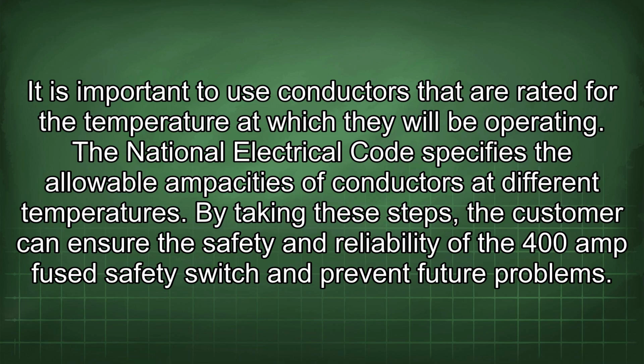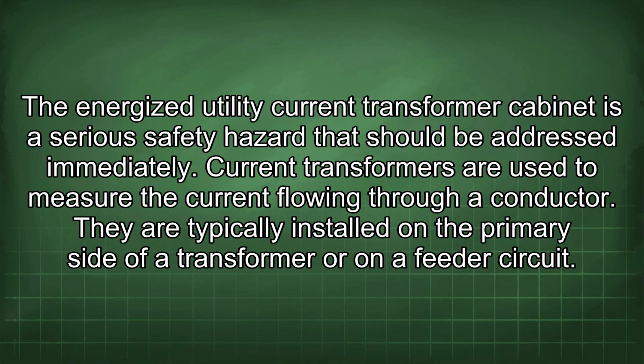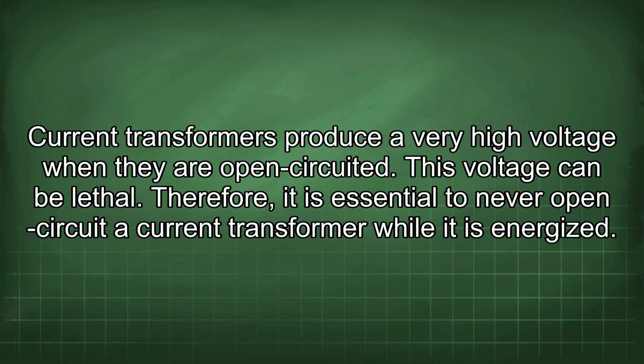By taking these steps, the customer can ensure the safety and reliability of the 400 amp fuse safety switch and prevent future problems. The energized utility current transformer cabinet is a serious safety hazard that should be addressed immediately. Current transformers are used to measure the current flowing through a conductor. They are typically installed on the primary side of a transformer or on a feeder circuit. Current transformers produce a very high voltage when they are open-circuited. This voltage can be lethal. Therefore, it is essential to never open-circuit a current transformer while it is energized.